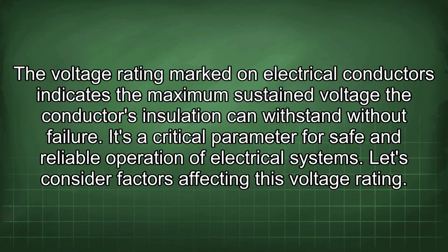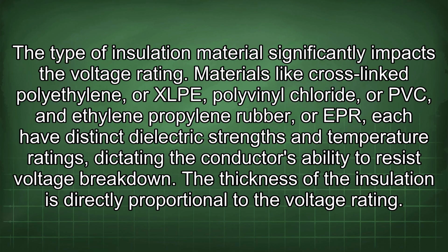The voltage rating marked on electrical conductors indicates the maximum sustained voltage the conductor's insulation can withstand without failure. It's a critical parameter for safe and reliable operation of electrical systems. Let's consider factors affecting this voltage rating. The type of insulation material significantly impacts the voltage rating. Materials like cross-linked polyethylene, or XLPE, polyvinyl chloride, or PVC, and ethylene propylene rubber, or EPR, each have distinct dielectric strengths and temperature ratings, dictating the conductor's ability to resist voltage breakdown.